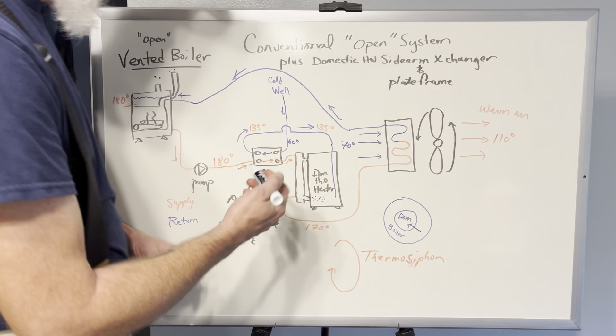If no water is running, no domestic hot water is being used, there's no water moving on the domestic side. So the boiler water won't have anything to give up heat to because this is stationary. No showers happening. Basically the heat transfers through that plate frame heat exchanger. If nobody's using hot water, the heat transfer in this plate frame heat exchanger is very little, almost nothing. You'll have some radiant losses and stuff like that. But basically the boiler water will go in, and in effect, it's not really going to give up any heat because there's no movement of water on the domestic side.